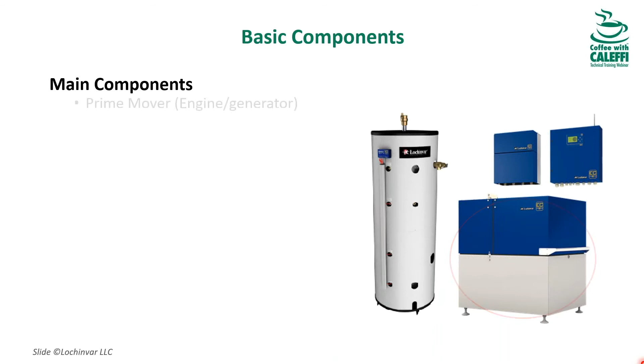We'll talk a little bit about the base components—common to basically all micro-cogens. We have the prime mover, which is the engine and generator. There's a heat exchanger, sometimes mounted within the system; in our case, it's mounted external to it. There's a control system, which can also be mounted within or outside the unit depending on the manufacturer. And there's a stratification storage tank.